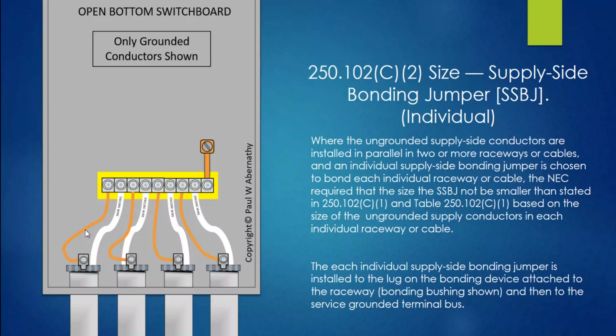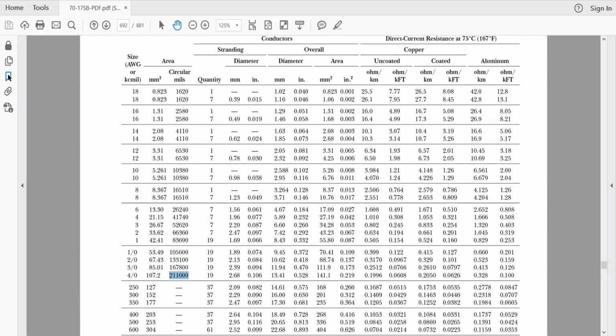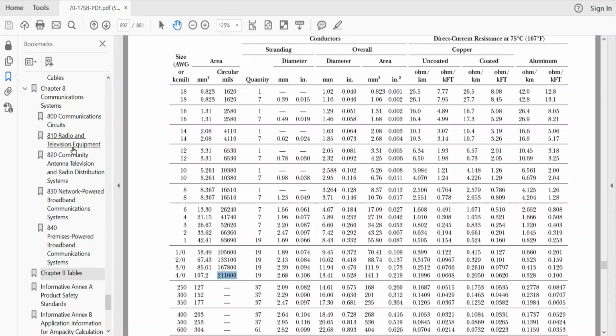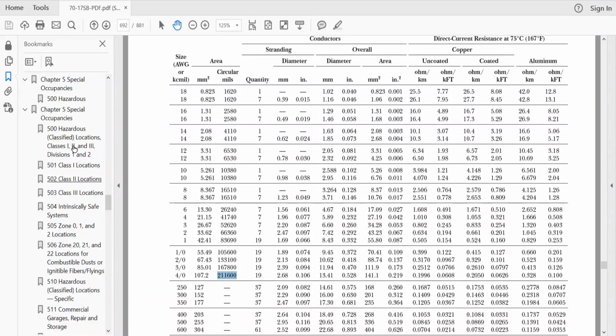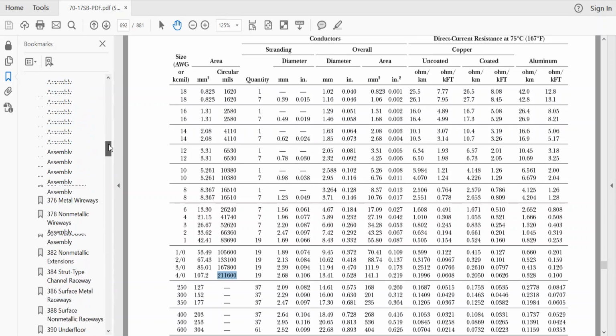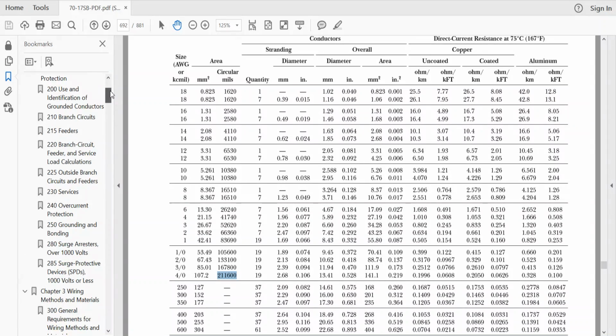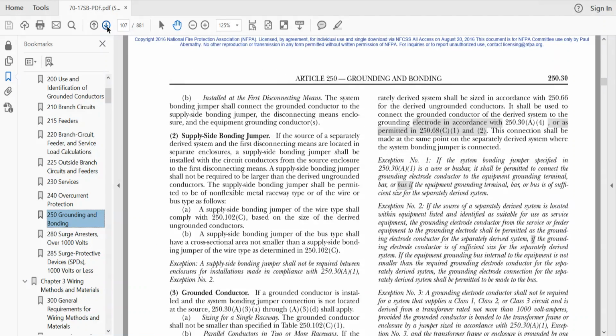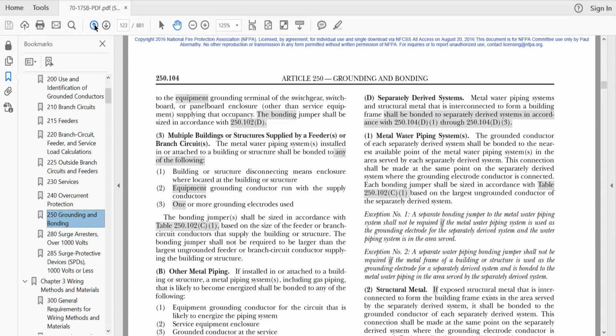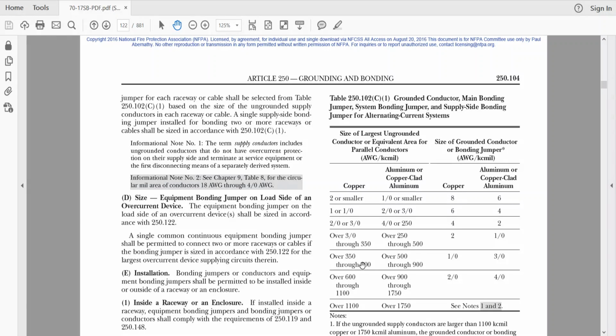Then this one's pretty easy. Then we're simply going to go to the table to do that. And simply going to the table, 250.102(C)(1) would determine the size we need. So let's go on. We've already done it, but let's go it again. So we're going to go back to the code. And of course, now I have to go all the way back to 250.102(C). And a lot of people out there will say, well, Paul, why don't you just use the search feature? And my answer to that is, I don't want to. I'm going to do it my way. I've been known to always do it my way. All right, so here's the table, and we determined it was 500, so over 3/0 through 350, it's not going to work. So here we got over 350 through 600. It needs a 1/0. Ours are copper for this example. All right.